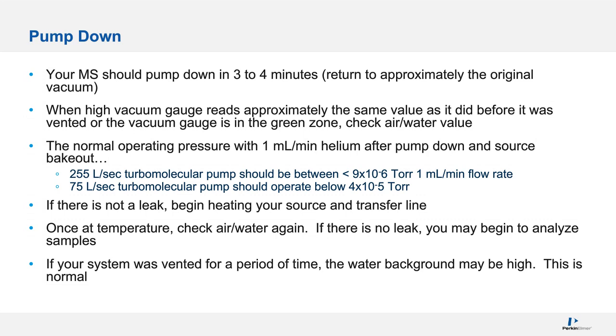This is why it's also nice to know your vacuum gauge. Now, if you start pumping and it's not pumping down immediately, it should start dropping immediately. If it's not doing that, possibly, and this happened to me once, I accidentally put my source back crooked, so the O-ring couldn't seal. That you usually hear, so you know it right away.